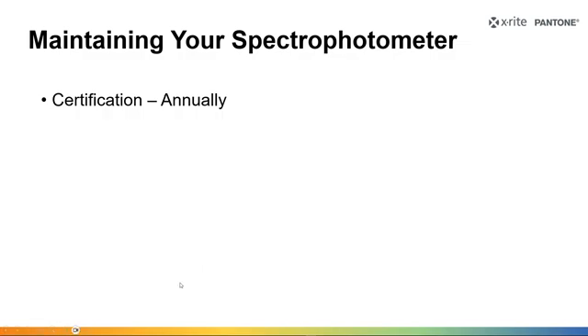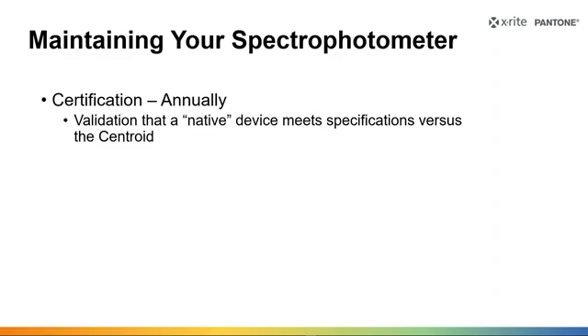Now, there is another step beyond that, and now we're at an annual basis. We went from daily or weekly to monthly, now to annual, and that is certification. So what is certification? It's kind of like Net Profiler, except that it's a validation that a native device meets the specifications versus the centroid. So typically this is happening when you send your instrument to X-Rite, right? It goes into our service center and we're putting it into this tightly controlled environment. Now we're going to test it and see natively, if I just measure similar to those tiles, does it pass the specification?